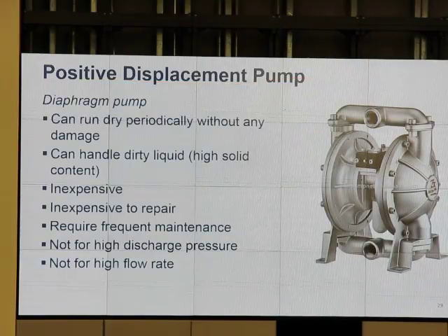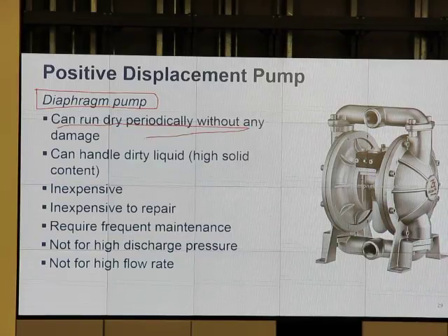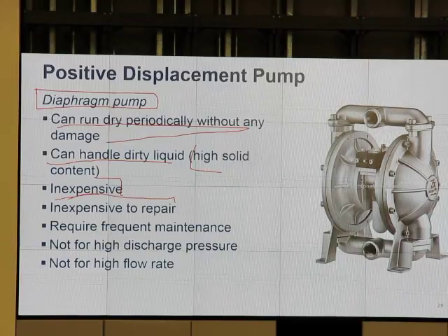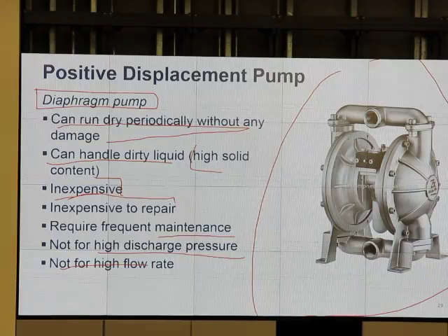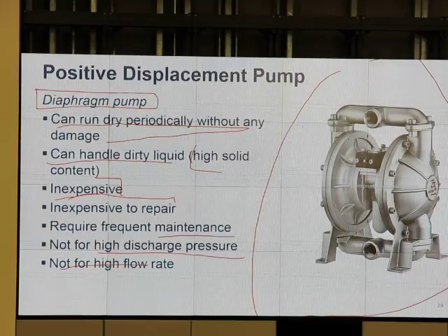Diaphragm pump. The name is diaphragm pump. You may want to memorize that in addition to knowing that it is PD. It can run dry periodically without any damage. It's good to handle dirty liquid, high solid content. Cheap or inexpensive to repair, requires frequent maintenance. Not for high discharge pressure, not for high flow rate, but it's good because it can handle a little solid. And the way it works, you have seen in the video already.